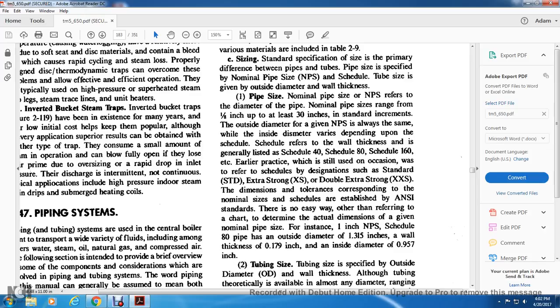Schedule refers to wall thickness and is generally listed as Schedule 40, Schedule 80, Schedule 160, etc. The earlier practice, which is still used on occasion, refers to the schedule by designations of standard, STD, extra strong, XS, and double extra strong, XXS. Dimensional tolerances corresponding with the nominal size and schedule are established by American National Standards Institute standards. There is no easy way other than referring to a chart to determine the actual dimensions of a given nominal pipe size.